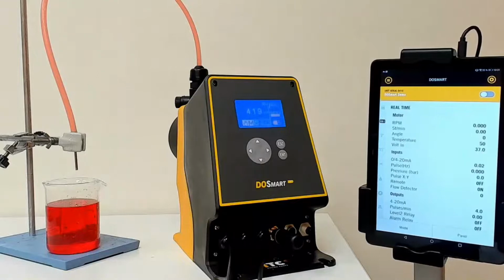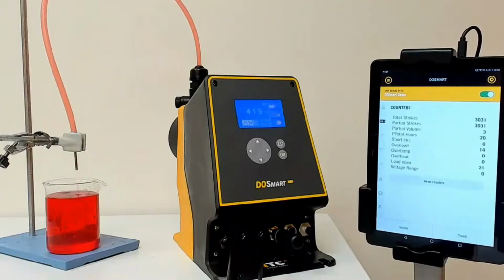And we have the monitor window where, while the pump is working, we can see all the motor parameters, all the inputs from the different sensors that are controlling the pump, and also the values of the inputs and the outputs for external signals. We have counters to know the number of strokes, the number of hours, and the volume delivered.